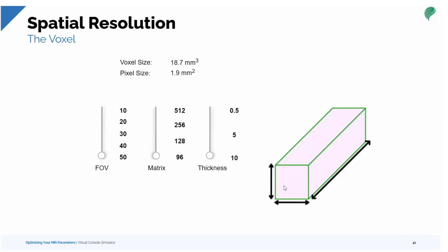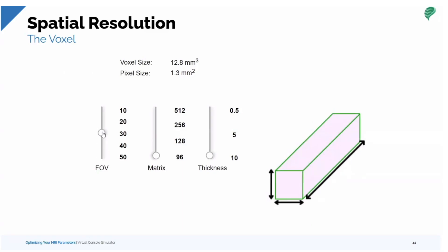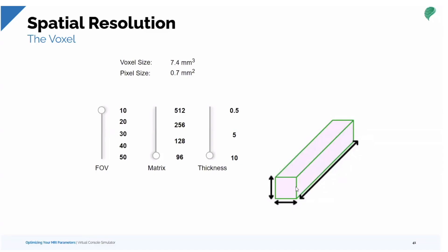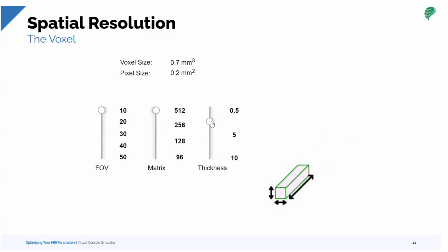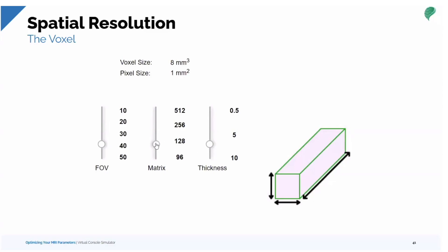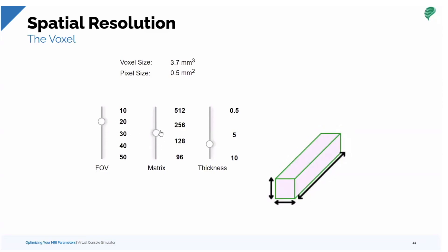A voxel is a three-dimensional cube. As field of view decreases, so does pixel size — the face of the pixel — measurable in millimeters. This is our geometry. The slice thickness controls the depth of the voxel. As the matrix increases, pixel and voxel sizes get smaller both mathematically and visually. Large voxels give us lots of signal but very low resolution. Small voxels give us very high resolution but lower signal-to-noise, so we have to compensate in certain ways.